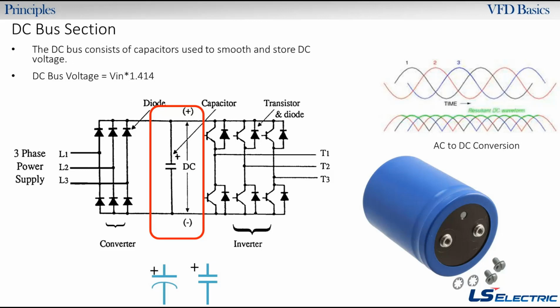And one of the other things that happens when you're rectifying AC to DC is if you look over here, at these graphs right here. So we have phase 1, 2, 3, which is AC. But when we're rectifying it, we have like this little line here, which are like these little humps. That's DC bus ripple, okay? And we want to smooth out that bus ripple so we have a nice solid DC bus voltage. So the more capacitors you put in there, and technically the more pulses you have, if you had a 12 pulse drive, you would have less DC bus ripple, so it would be a smoother DC bus. And that also helps out with some other things such as harmonics, which we don't talk about too much in this webinar, but that's something people are always concerned about, is the harmonics or the noise generated from the drive. Okay, so that all comes down to these diodes.